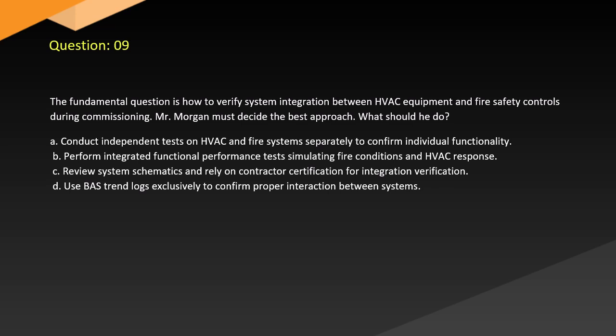Question 9. The fundamental question is how to verify system integration between HVAC equipment and fire safety controls during commissioning. Mr. Morgan must decide the best approach. What should he do? A. Conduct independent tests on HVAC and fire systems separately to confirm individual functionality. B. Perform integrated functional performance tests simulating fire conditions and HVAC response. C. Review system schematics and rely on contractor certification for integration verification. D. Use BAS trend logs exclusively to confirm proper interaction between systems.